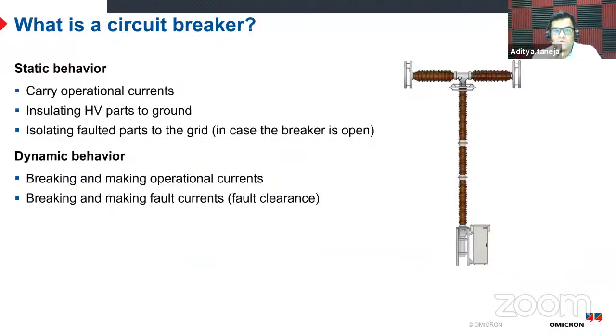However, I will try to make it small, and let's see what a circuit breaker is required to do. In a static condition, when it is not moving, it is required to carry the operating currents and insulate the high voltage paths from the ground. There is a high voltage part and there is a ground, and it should provide the insulation between them. It also should isolate the faulted parts of the grid. If the breaker is open and there is a fault on one side, the breaker should provide insulation between the faulty part and the healthy part of the network. That is the static behavior.